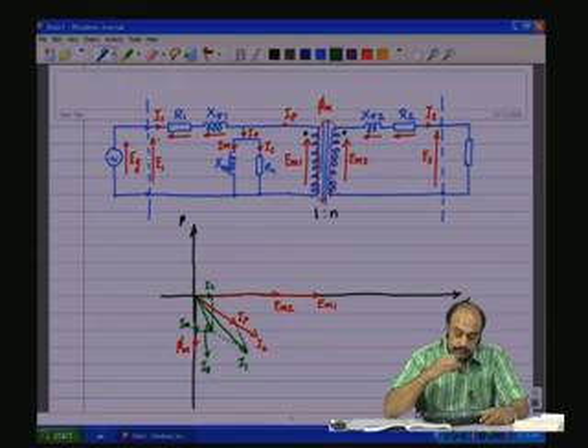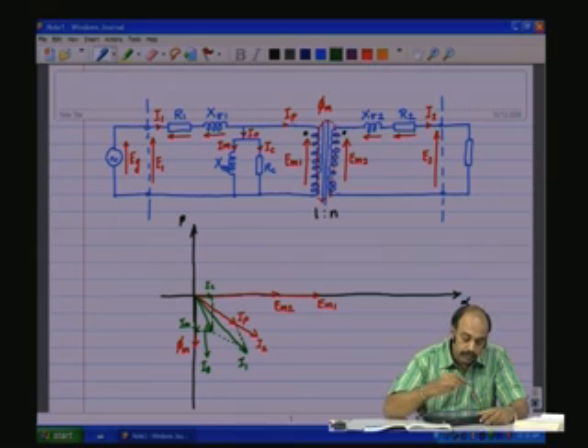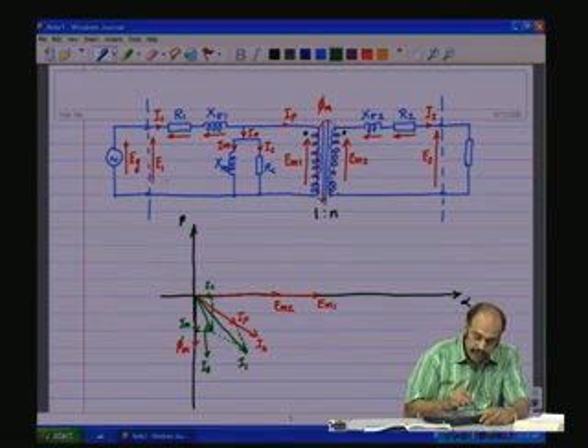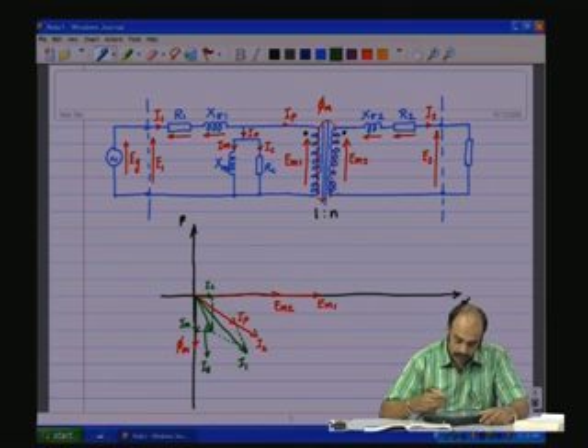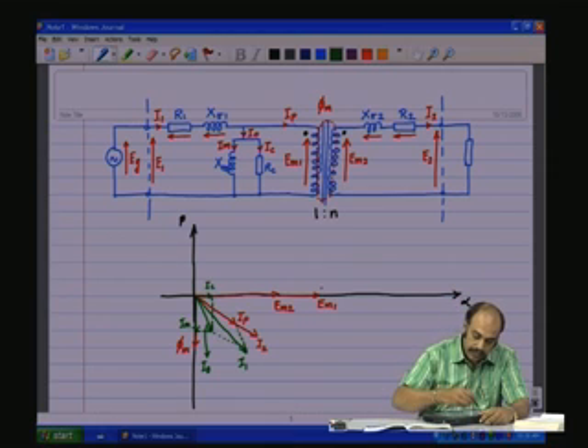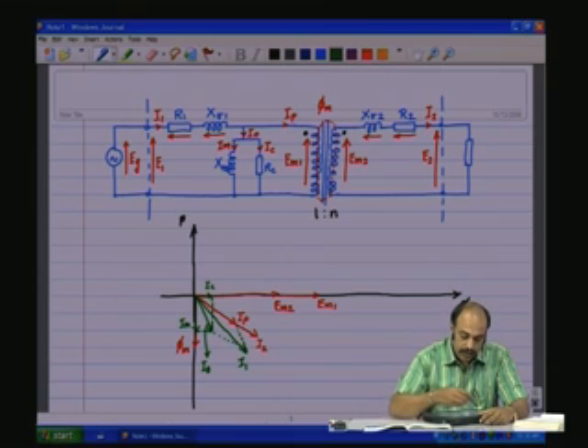Now what is E1? The terminal voltage E1 is the voltage across this terminal, which is EM1, plus the voltage across the leakage reactance, plus the voltage across the winding resistance R1 of the primary. All these are vectorially added to obtain E1. So we have EM1 here. So to EM1 we add, let us say, IR1. Now IR1 will be in phase with I1.